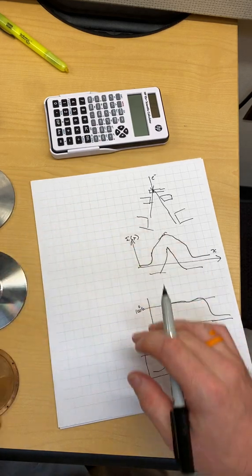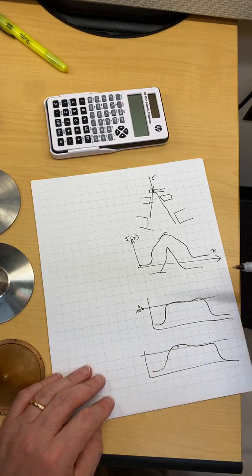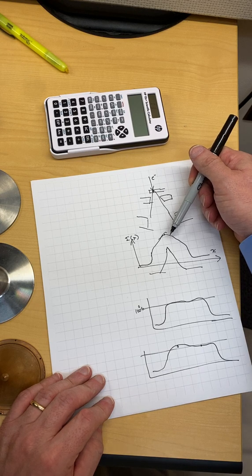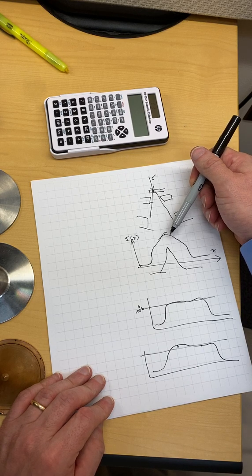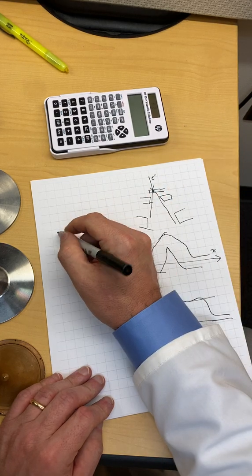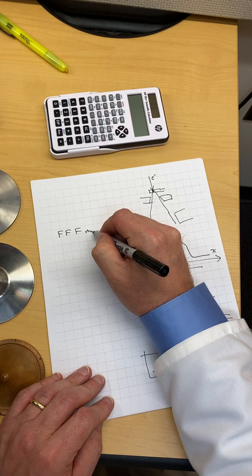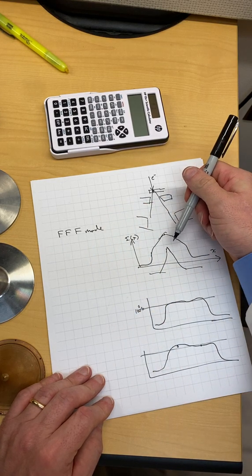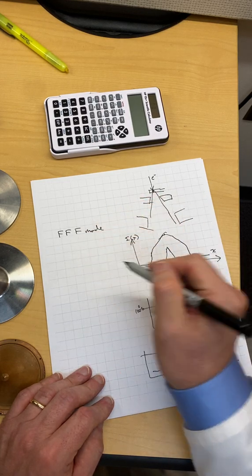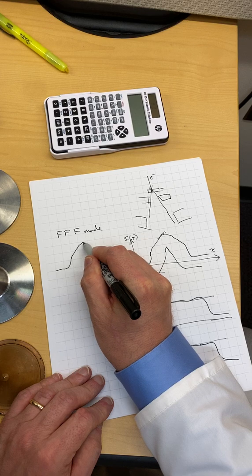And then these days, because we have full VMAT beams, you can easily ask the question, why do we even need this? If we're going to do intensity modulation using VMAT, we can simply use the non-flattened beam. And this is the flattening filter-free, flattening filter-free mode of the LINAC. And in the flattening filter-free mode, this is gone. There's a hole in the carousel. You get this full-peaked X-ray beam out of it. It looks something like this.